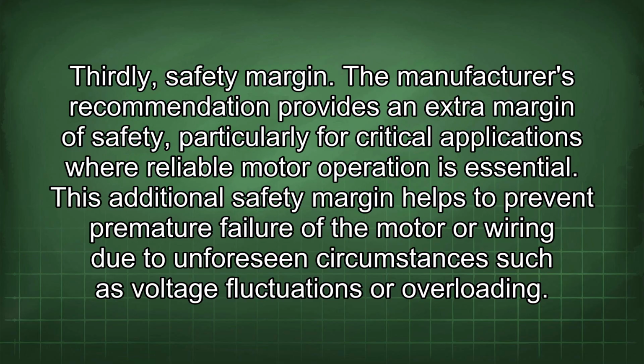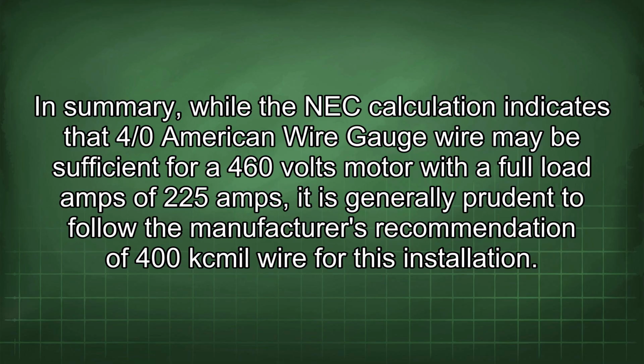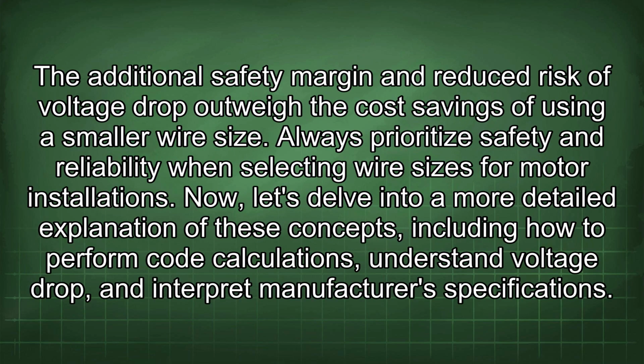This additional safety margin helps to prevent premature failure of the motor or wiring due to unforeseen circumstances such as voltage fluctuations or overloading. In summary, while the NEC calculation indicates that 4/0 AWG wire may be sufficient for a 460 volt motor with a full load amps of 225 amps, it is generally prudent to follow the manufacturer's recommendation of 400 kcmil wire for this installation. The additional safety margin and reduced risk of voltage drop outweigh the cost savings of using a smaller wire size. Always prioritize safety and reliability when selecting wire sizes for motor installations.